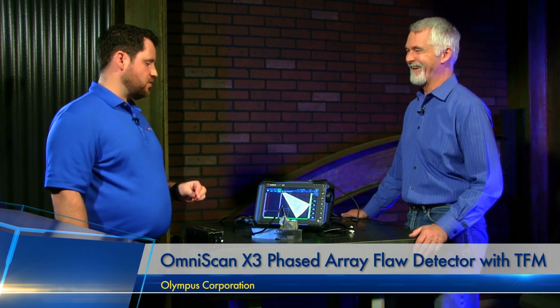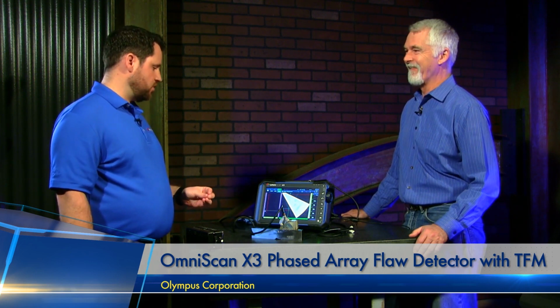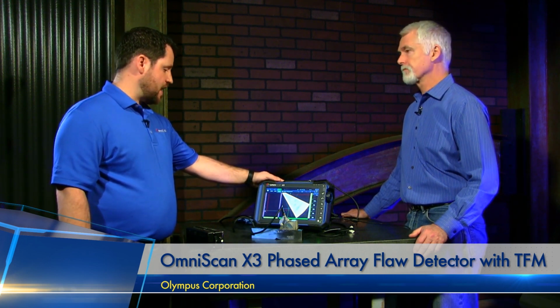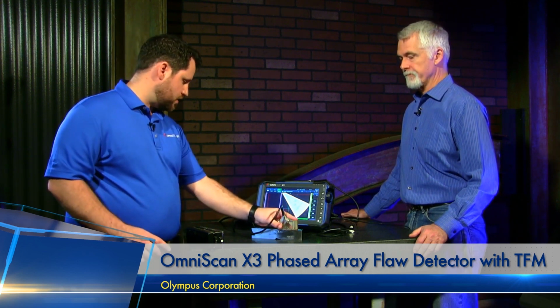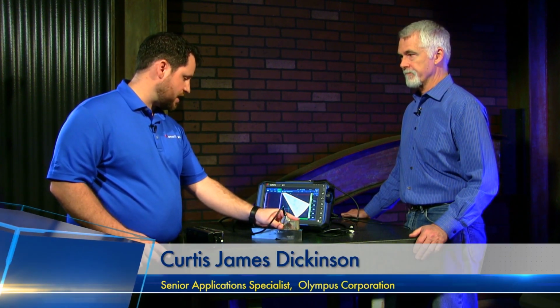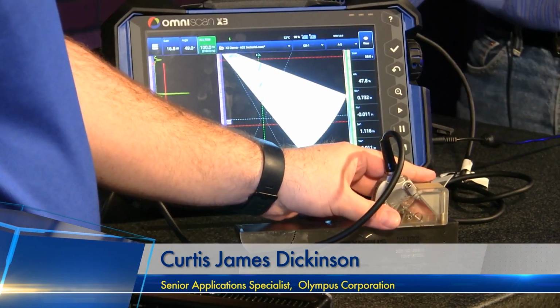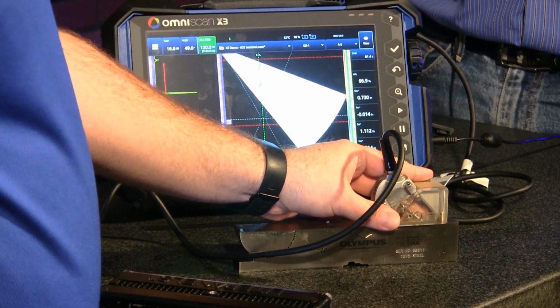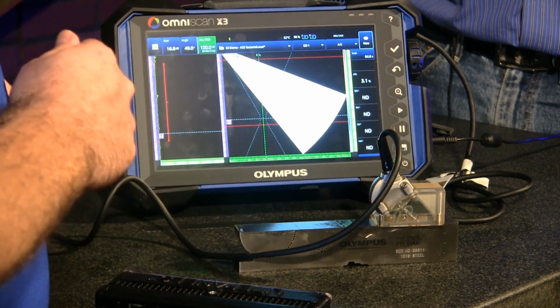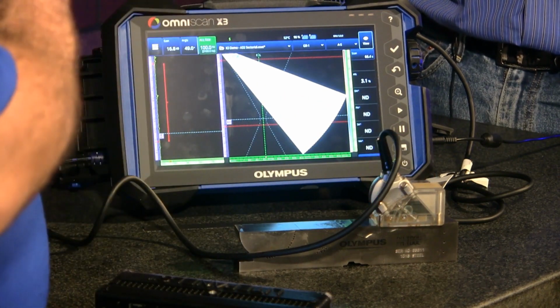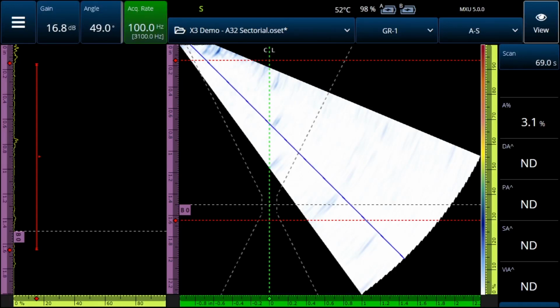Very much so. One of the other additions that we tried to include outside of just the software improvements, so just the workflow that you go through for setup and calibration, we also tried to make some hardware improvements to the system. And that correlates to the resolution of the signal that we have on the display. We've added what's called a 16-bit A-scan for this system. So we have a lot more data that can be used to represent the A-scan signal, which correlates to a higher resolution signal that really pops on the display.